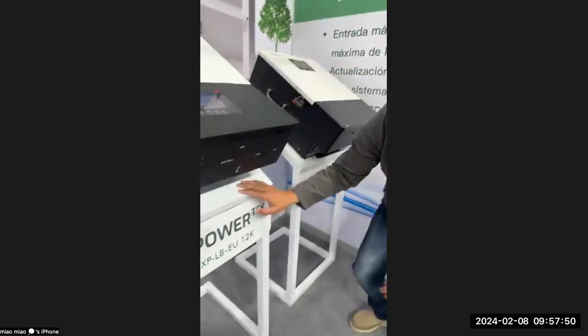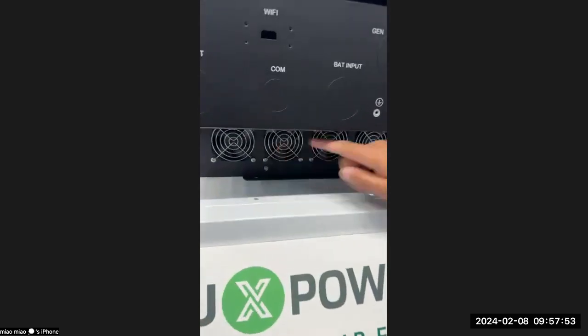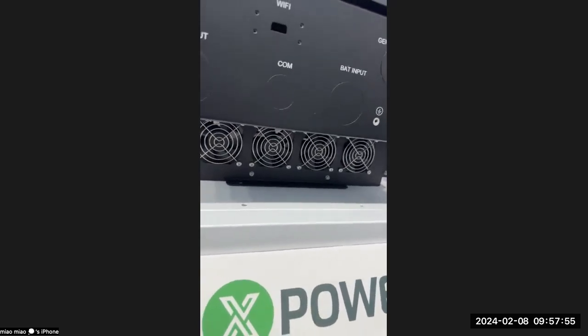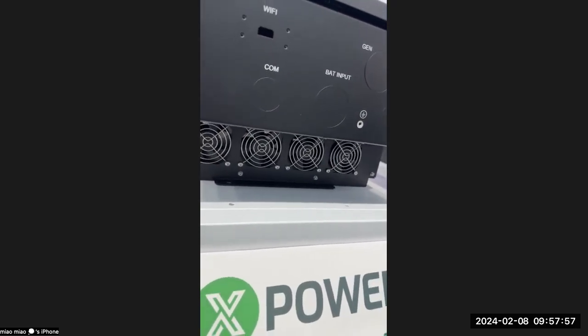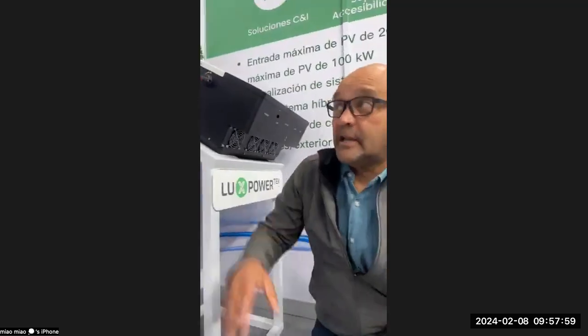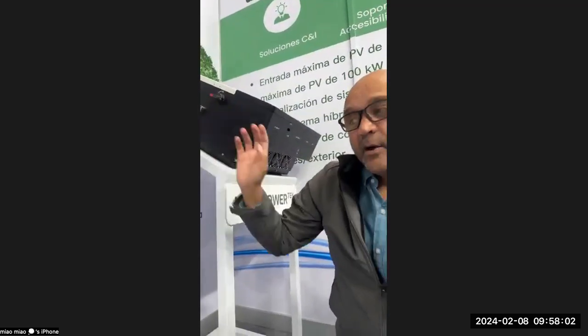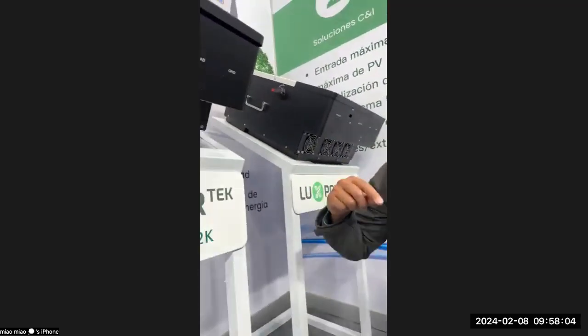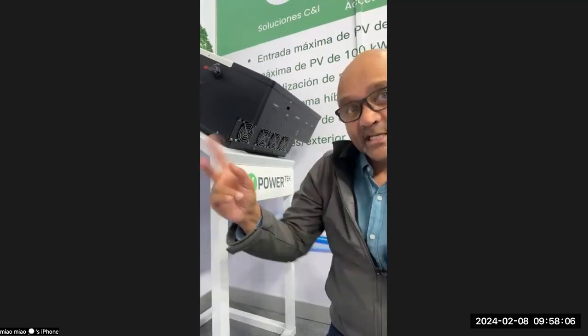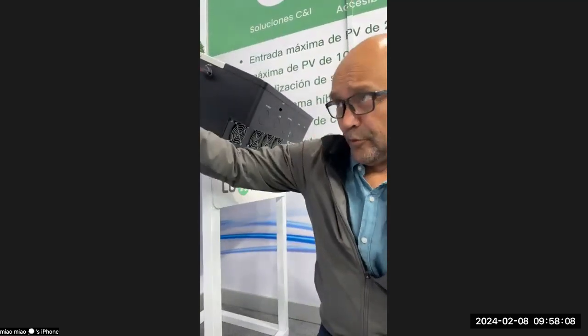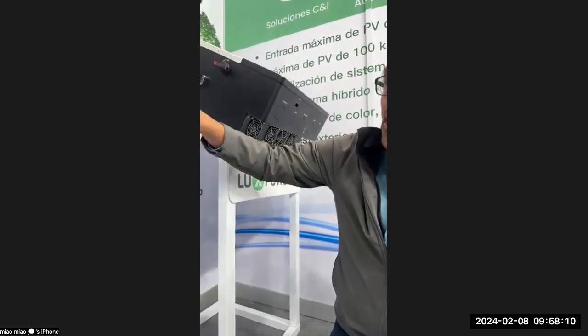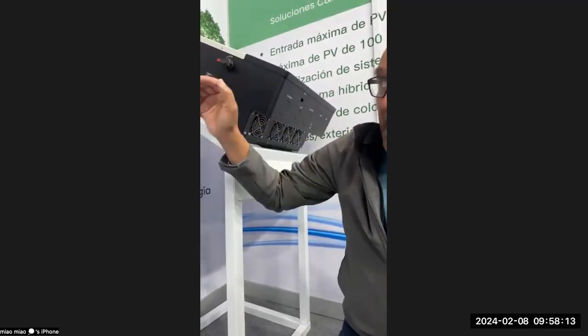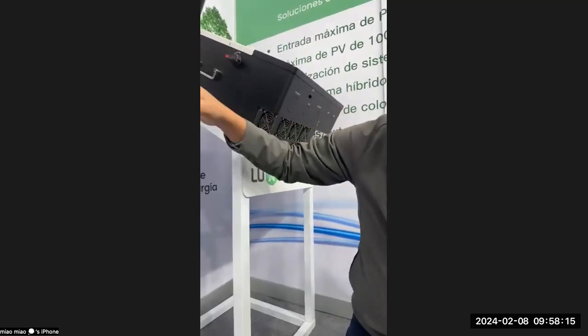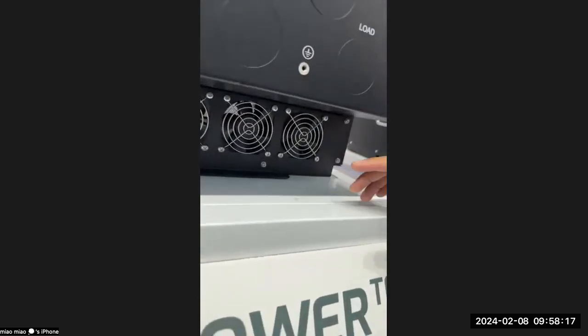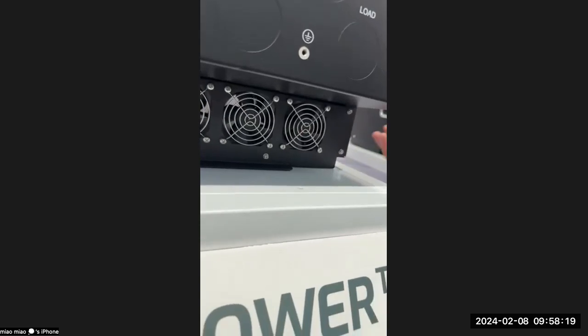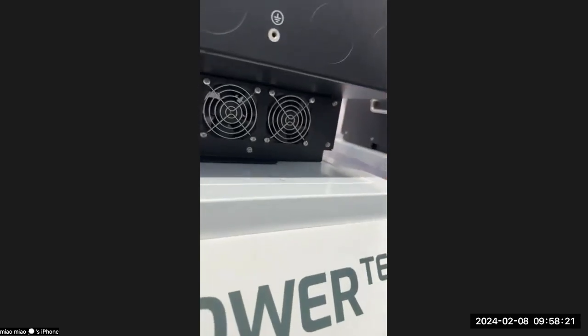But if you have a look underneath here, you'll see that the 12 and the 10 come with cooling fans. The cooling fans only operate when the PV or the output function of the machine exceeds 6 kilowatts, especially on the 12, you'll find the fans come on. The fans do not blow air inside the machine. Underneath here or inside this box, there is a massive heatsink, and the fans simply cool the heatsink. We've got thermocouples inside here as well as inside the machine.